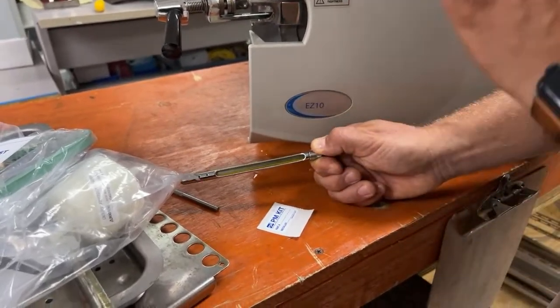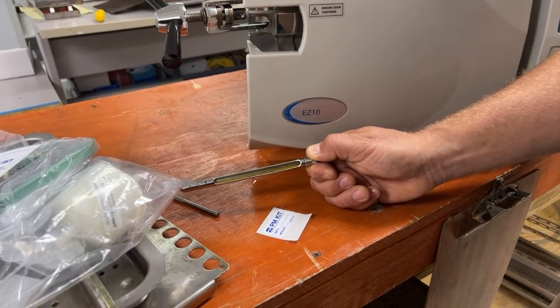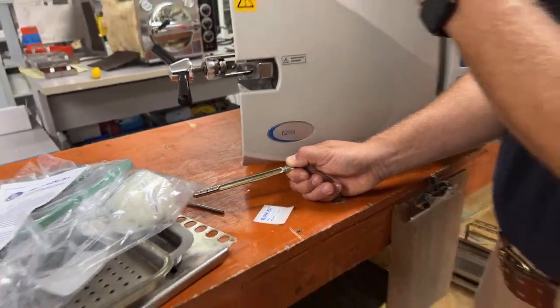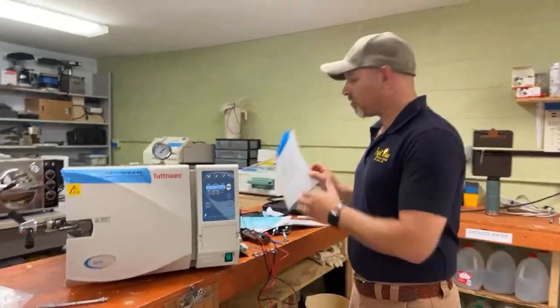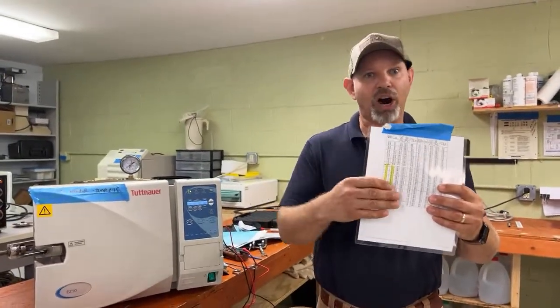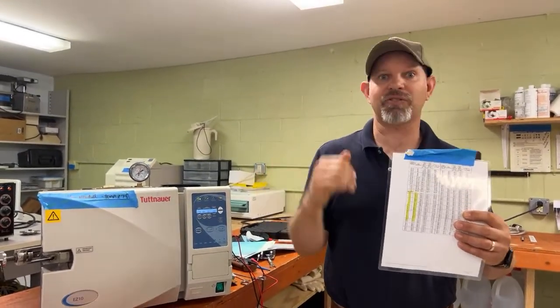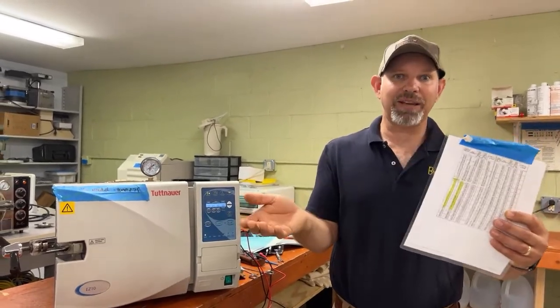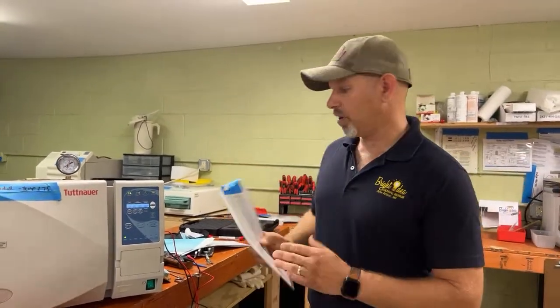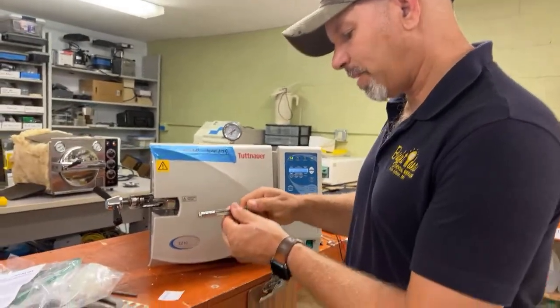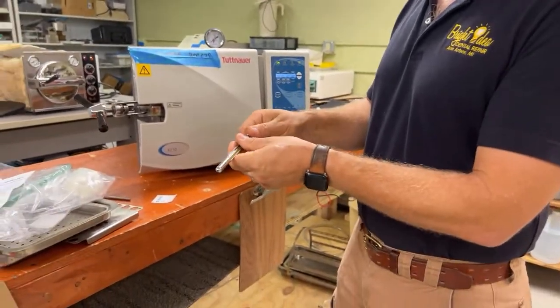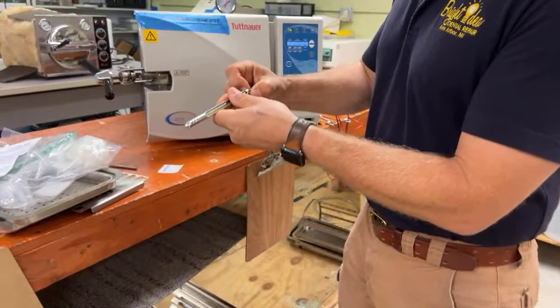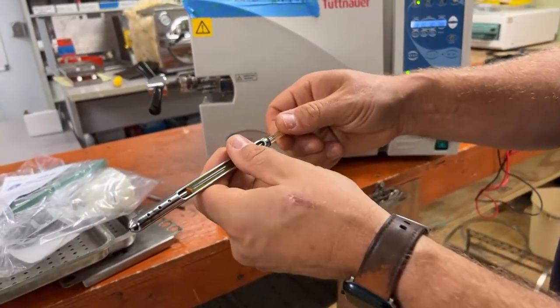One thing that's important to know is that if your pressure is verified to be good, then your temperature has to be where your pressure is. These two numbers are tightly correlated to one another. It's a fact. If you have 30 pounds of pressure, you have 270 degrees in the steam environment. If you don't have the right temperature, then you have some sort of pressure leak somewhere. Now, I think what might have happened with this, and I don't know, is pretty sad. I'm kind of afraid of what I'm going to see here. But why not? So we're going to look at this.